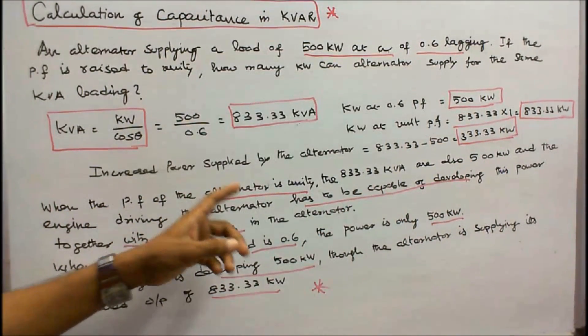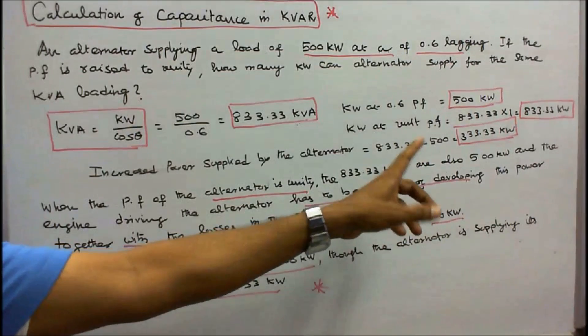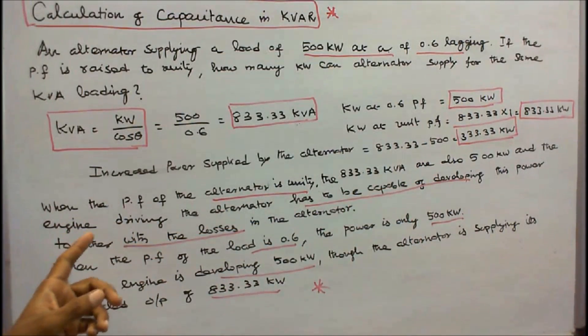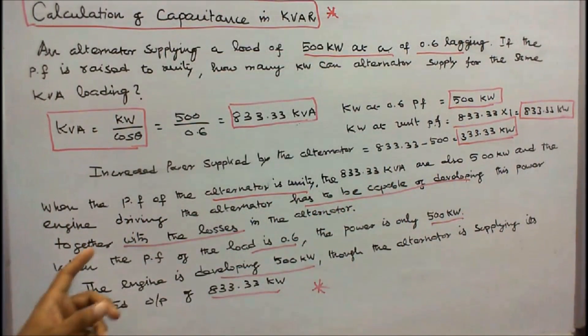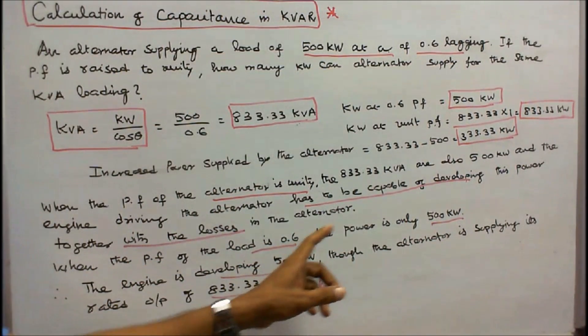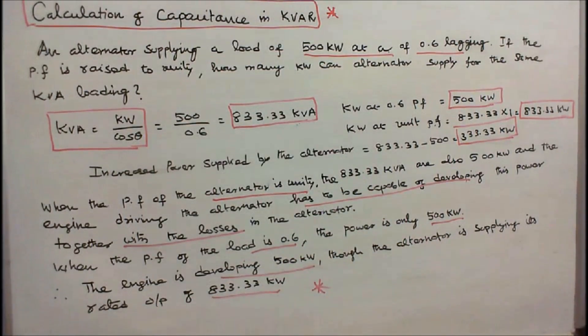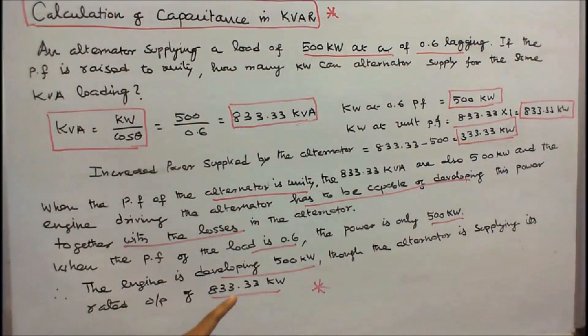When the power factor of the alternator is unity, the 833.33 KVA are also 833.33 kilowatts, and the engine driving the alternator has to be capable of developing this power together with the losses in the alternator. When the power factor of the load is 0.6, the power is only 500 kilowatts, so the engine is developing only 500 kilowatts, even though the alternator is supplying its rated output of 833.33 KVA. This is the importance of power factor improvement. With this, I conclude my lecture — thanks for listening.